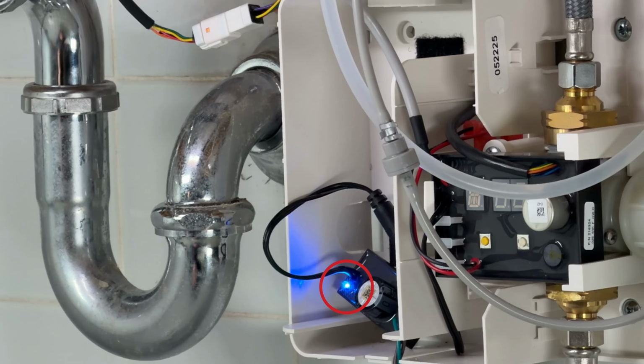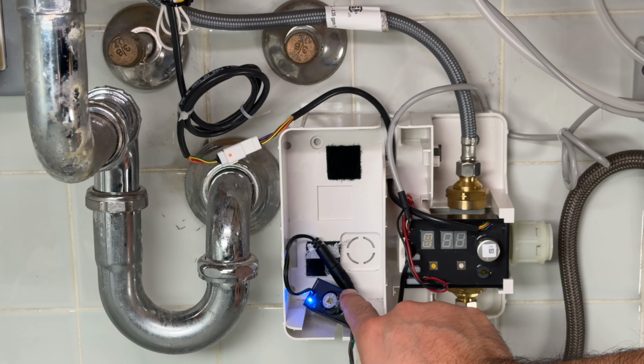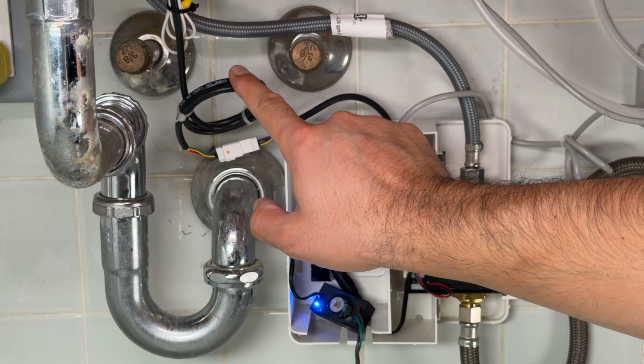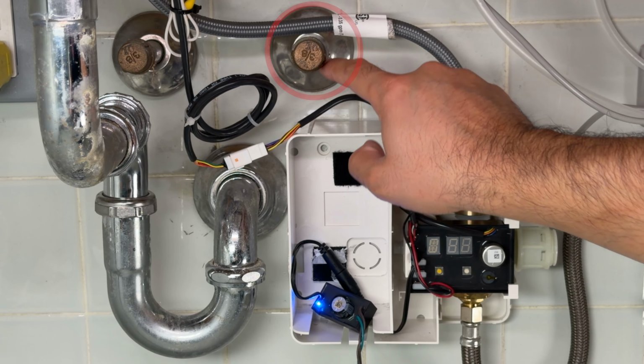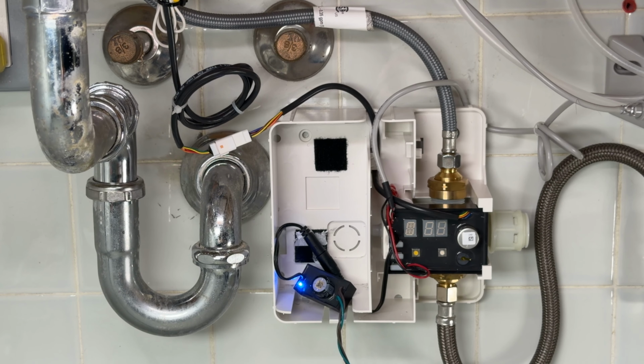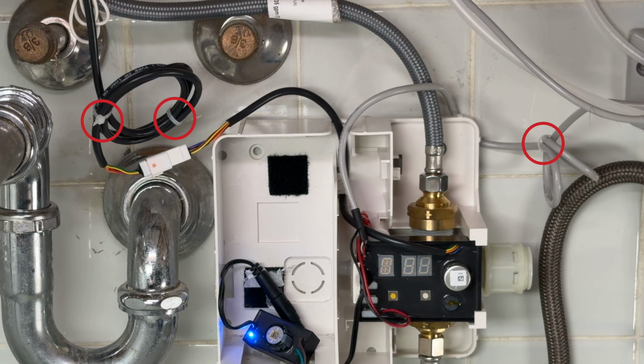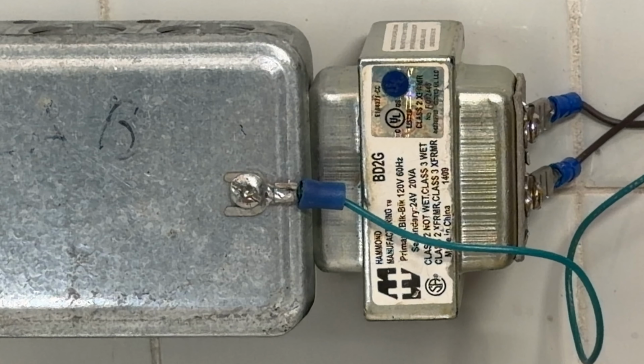The next thing that we want to check is the wiring. Are the wires in contact with other electrical components or any metallic surfaces? If so, you may need to clean up the wiring. All of the cables should be organized and neatly routed using the plastic cable ties that are provided with the unit or other suitable methods to avoid touching any conductive surfaces. This could be causing grounding failures. The green ground wire off of the converter must be grounded to a proper building ground.